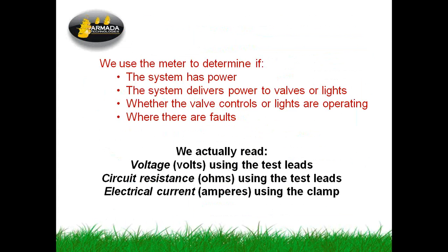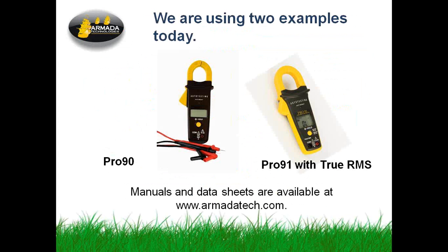What we have to do then is take what the meter is telling us and convert it into those real world things. And so down below you can see what we actually read with the meter is volts, voltage in volts. Using the test leads, we measure resistance in ohms, and then we can put the clamp around a wire and we can measure the current in amperes. Now those things all by themselves aren't really useful until you know what the importance is or what the range of those readings actually means to you when you're trying to troubleshoot or check your system. And I'll go through a little list of those things here in a second.